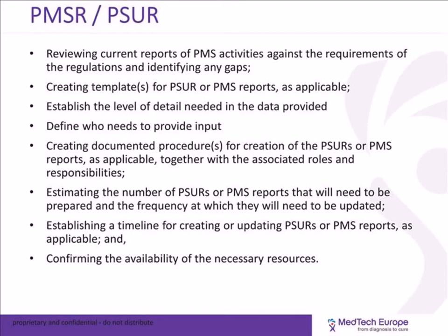Establishing the level of detail. I mean, the devil is in the detail. We probably should err towards giving the information required and not more information, so that the workload is manageable for us. It in part will depend on the output of the comitology group on PSUR, defining the guide and the format. Create procedure. So we need to have a procedure, which will be audited by the notified body, on the creation of these reports.